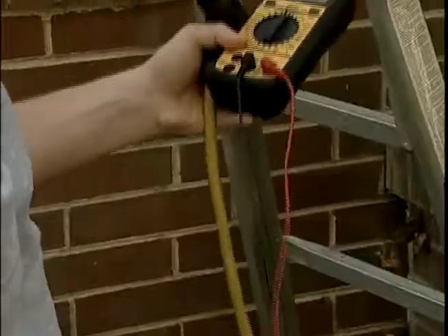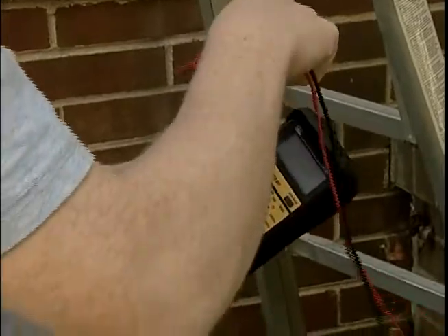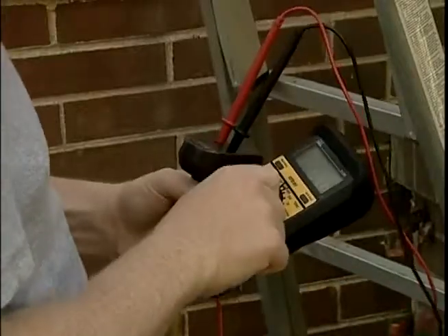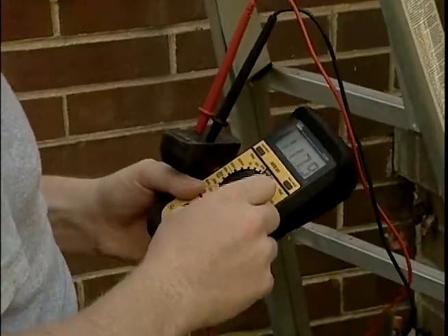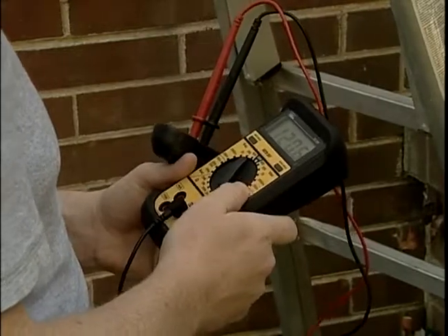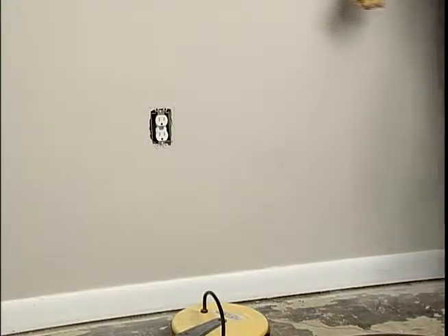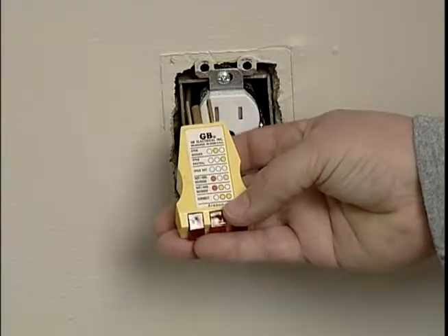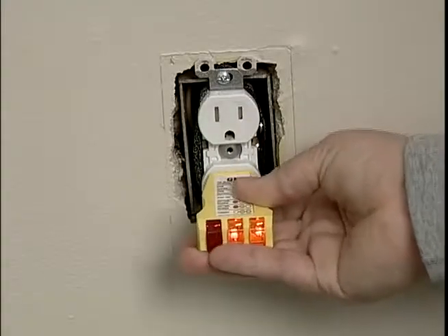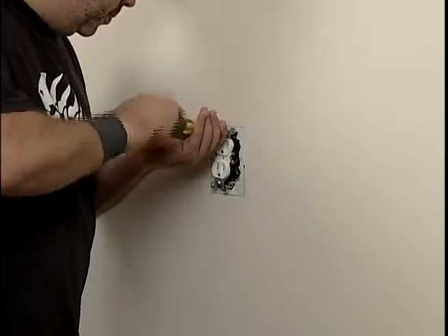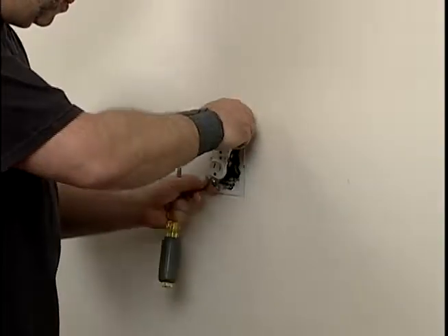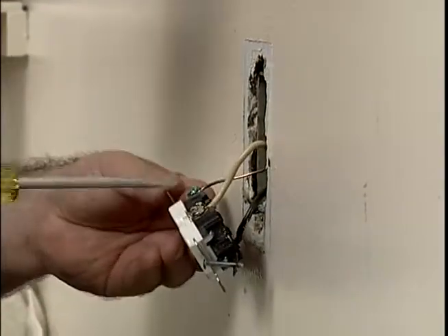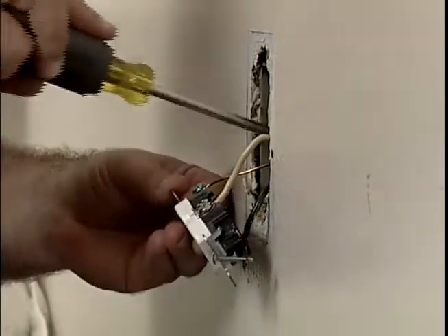This test must be performed on all extension cords, cord sets, and receptacles that are not part of the permanent wiring of the structure that is being erected. Any equipment that is connected to an electrical power source via a cord and plug must also be tested. This test may be performed using a simple continuity tester, such as a lamp and battery, a bell and battery, an ohm meter, or a receptacle tester. Additionally, each receptacle, attachment cap, and plug on the job site must be tested to make sure that they are correctly attached to their grounding conductors, and that the grounding conductors themselves are connected properly to their terminals.